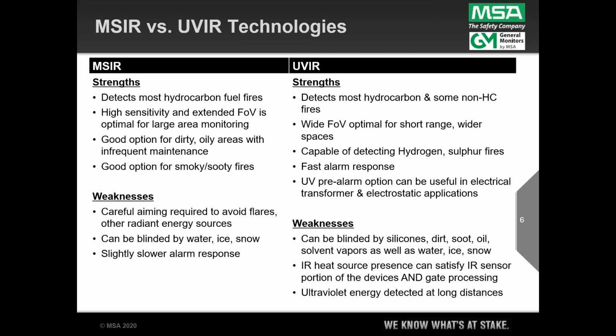And now our device as well, and some of the others in the market too, have a pre-alarm option. And where we have seen this useful for UV only is in transformer applications or electrostatics, where some sparking and arcing may actually be a precursor to an actual ignition. So one transformer hall I was working on on the West Coast, they used that UV pre-alarm specifically to alert the techs on site that, hey, we're having some sparking, we're seeing some energy that shouldn't be there, and the breakdown of insulation resistance is normally the root cause of that.